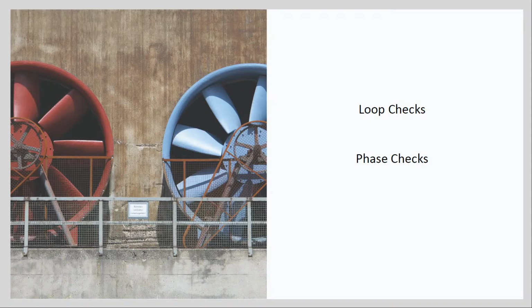You can do this on larger power systems by just visually verifying, say, like a high voltage transmission AC switch yard. You can visually see all the conductors, and you're going to confirm that everything is connected correctly from transmission lines to the buswork in an AC station. For smaller power systems, they can be measured. You can measure each phase and confirm that they're correct. You can also use a phase rotation meter that can be connected to the equipment before the power is terminated to the equipment, and that will tell you if your phases are connected correctly.